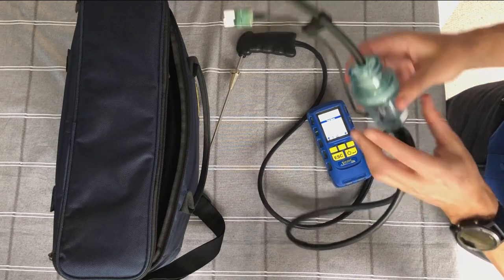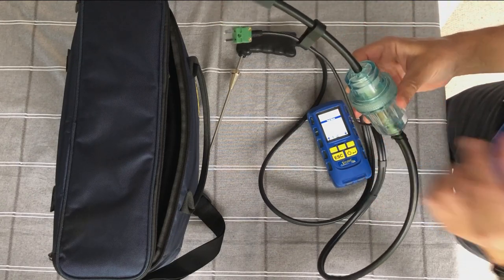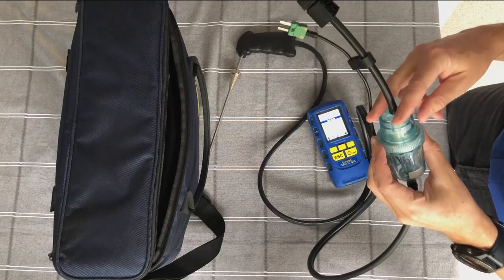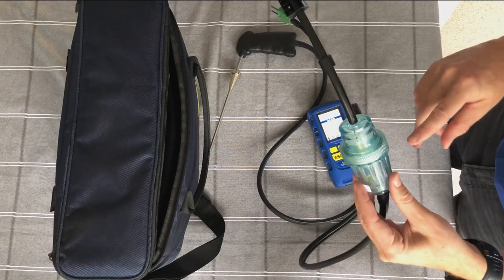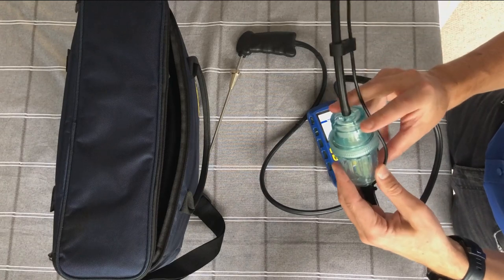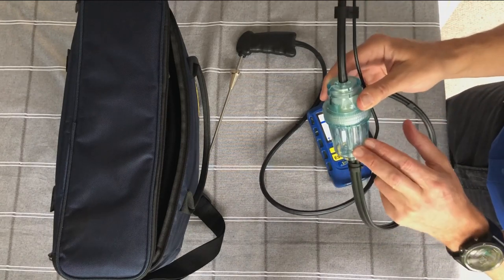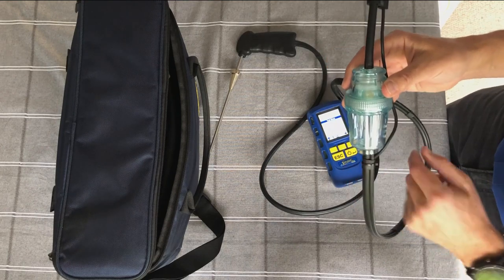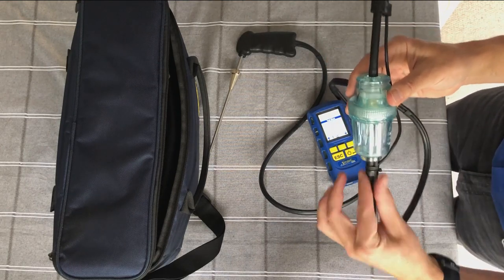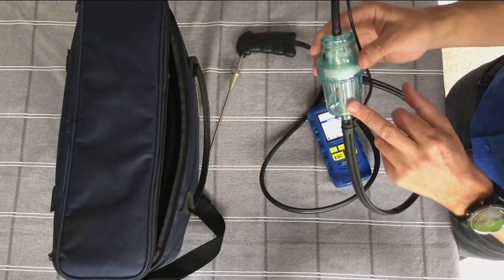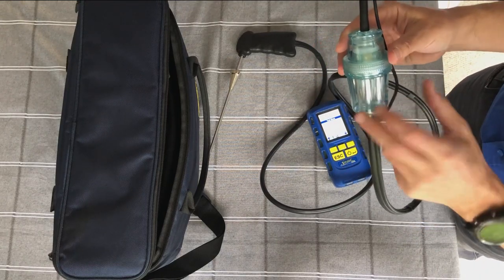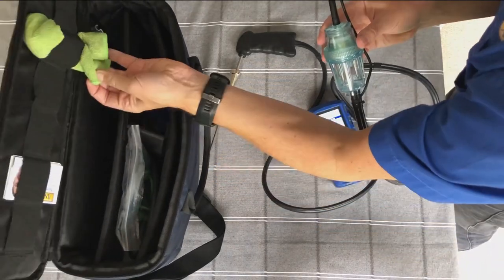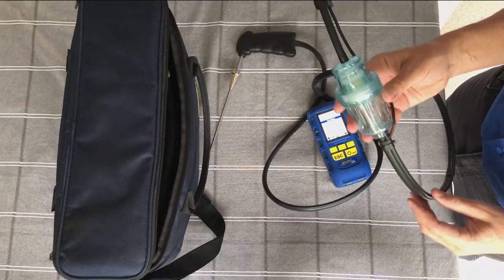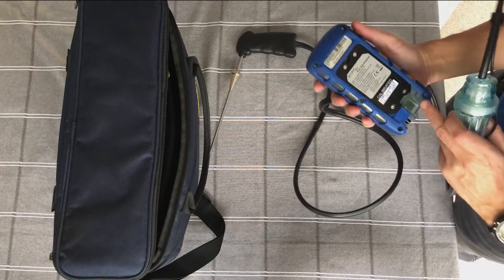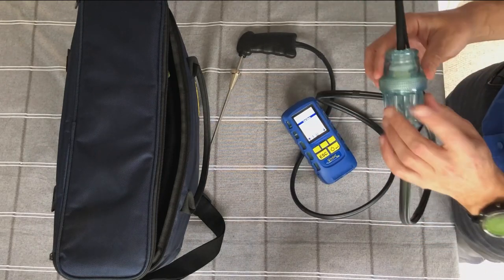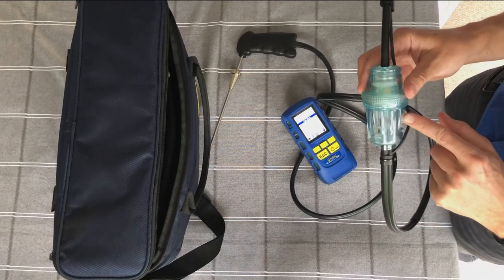The other end we've got the water trap and condense trap. This is a really, really important part of the overall design of the flue gas analyzer. This is where a lot of the filtration is housed, and it's got your condense trap for collecting any condense that might be sucked in or form as it cools as it comes up these tubes. So keep an eye on this. It's best to keep it emptied at all times. So when you start getting a bit of moisture in here, do use a cloth. I carry a cloth with me for getting in there and drying it out. And rather than it being in the back of the instrument like some of our competitors, top or bottom, we prefer to have it in line because it allows you to really dry this out thoroughly.